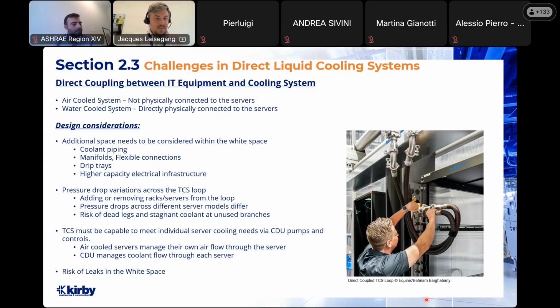In a liquid-cooled system, the technology coolant system must be capable of meeting the individual server cooling needs via the CDU pumps and controls. In an air-cooled system, so long as you have the air available in the space, the air-cooled servers manage their own airflow through the server. They generally have fans on them, and they pull their own air through and manage their own air. But on a liquid-cooled system, the CDU manages that coolant flow. The CDU manages the coolant flow through the TCS system, through the manifold, and then through the server. So it's a different approach. It's a different way of managing and controlling the system.